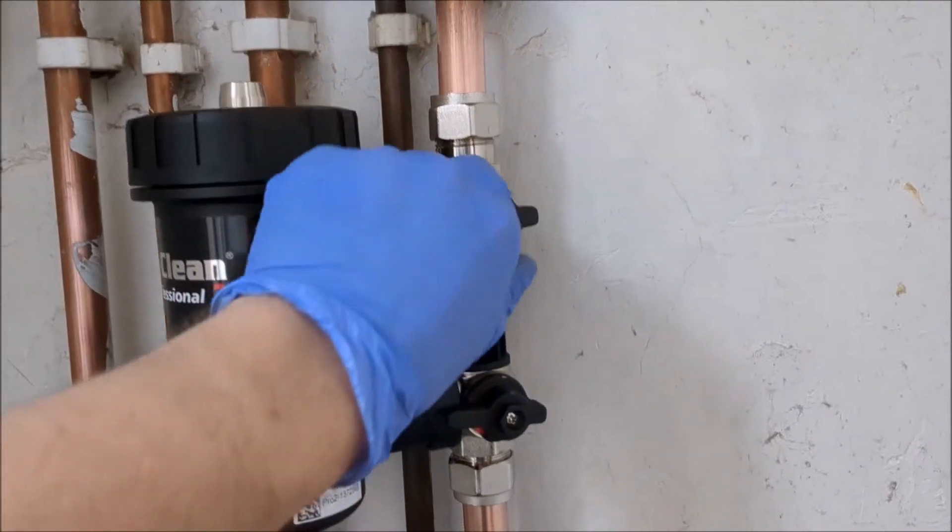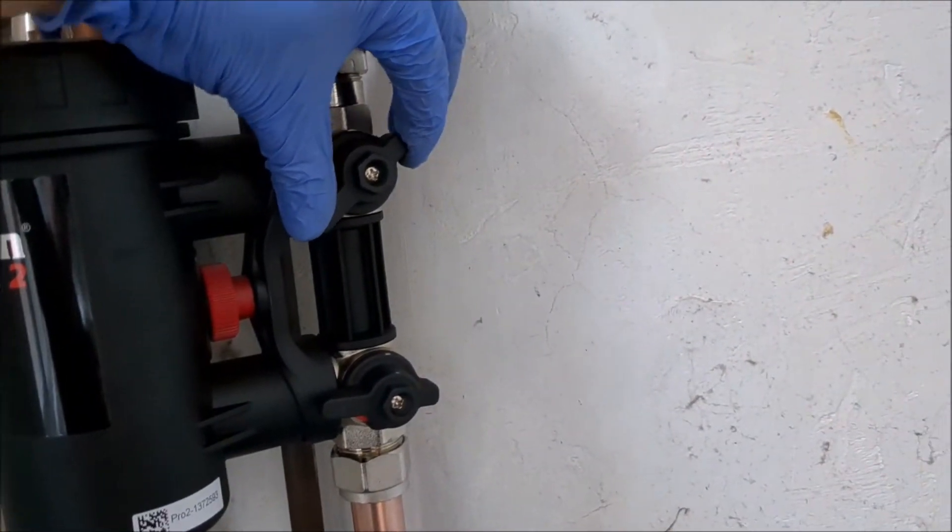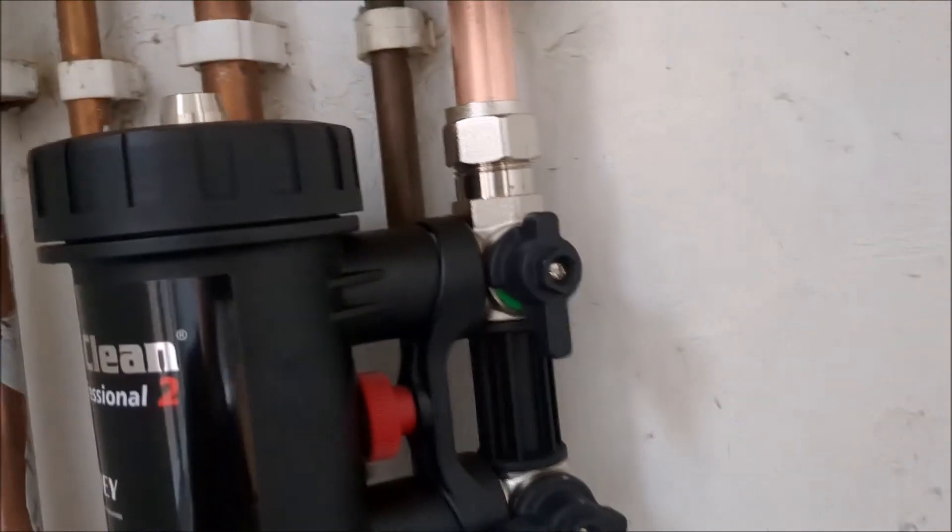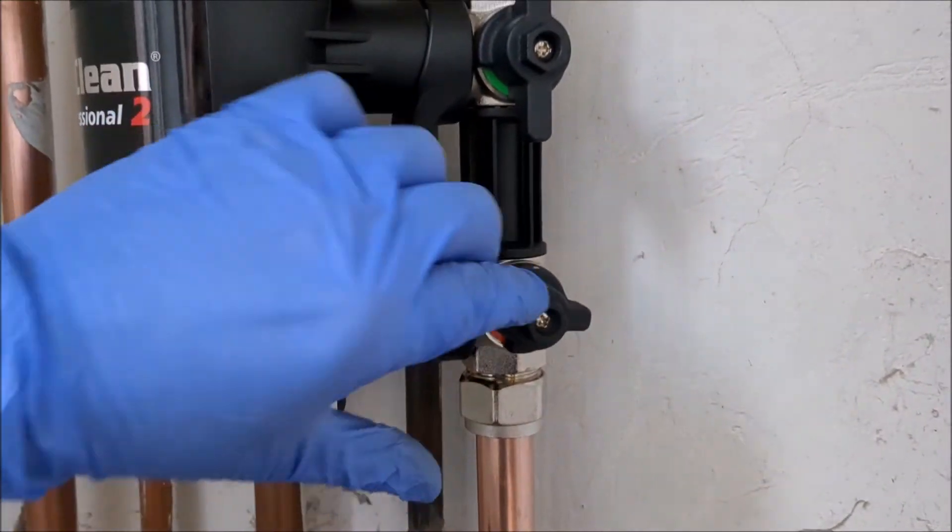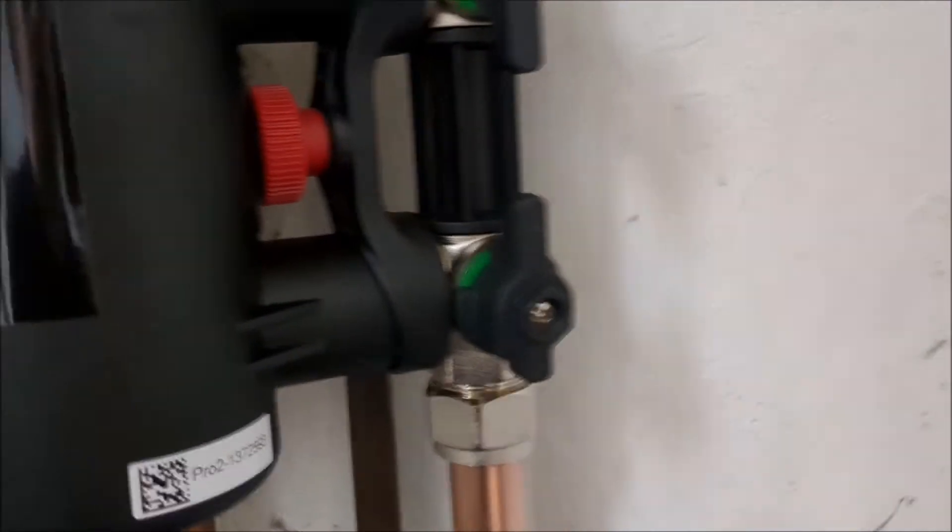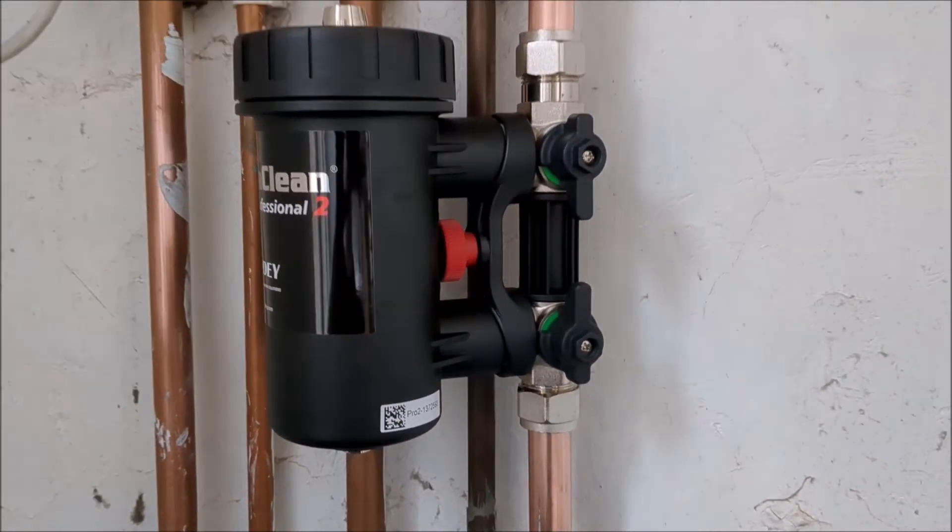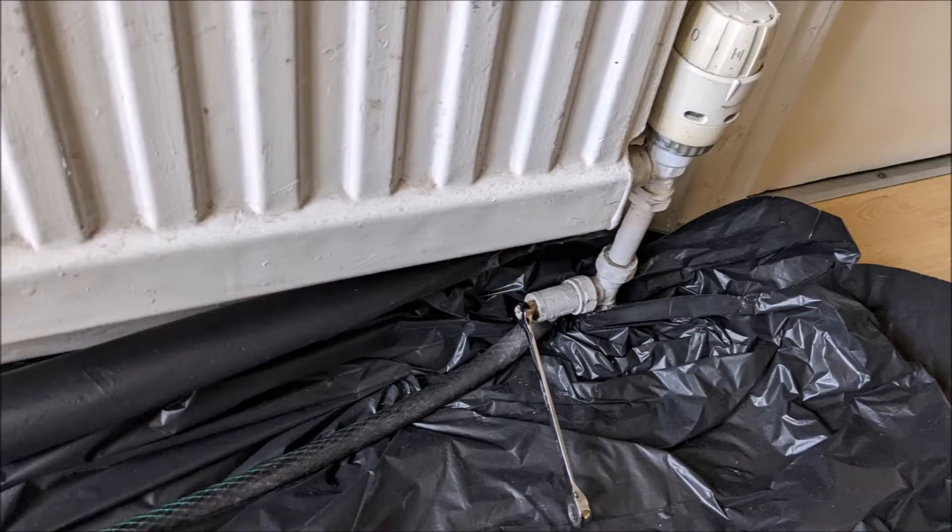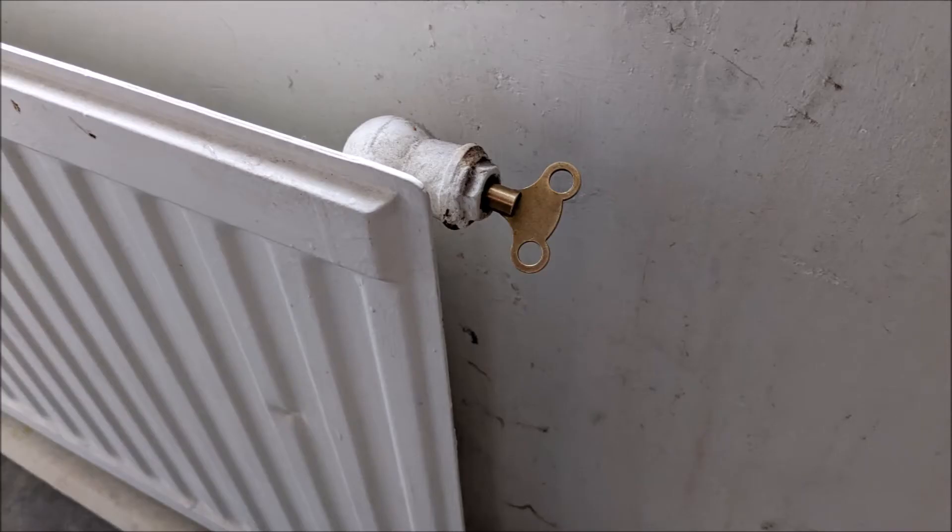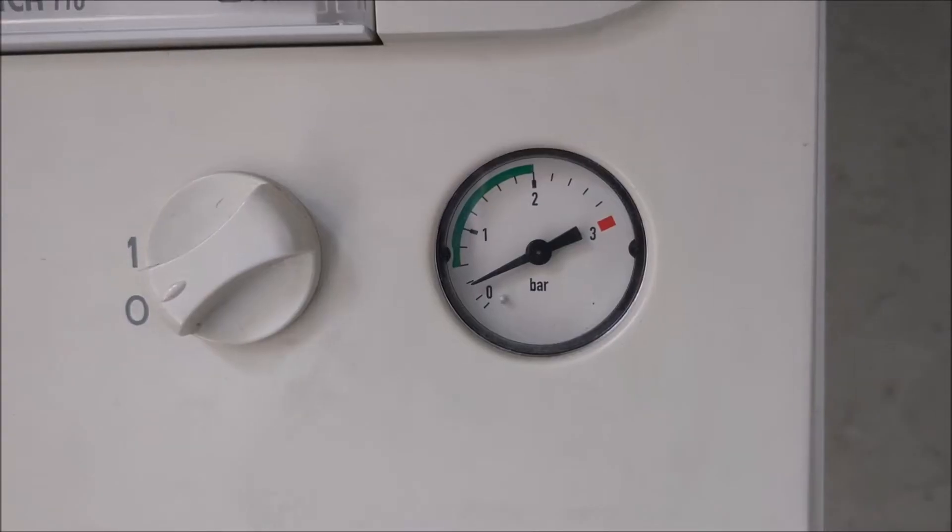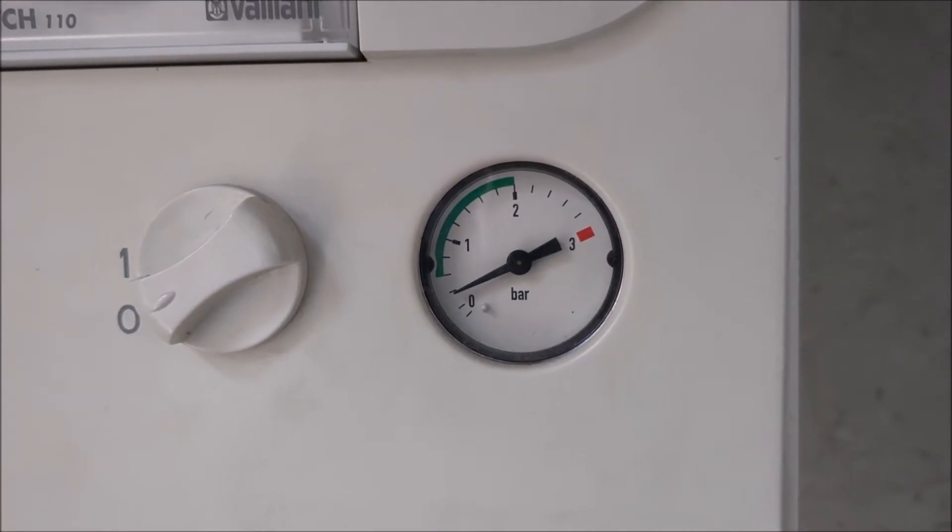Open the quarter turn isolation valves. To refill the system, close the drain valve and remove the hose pipe from the radiator. Make sure all the radiator bleed valves are closed. Use the filling loop to achieve the required pressure.